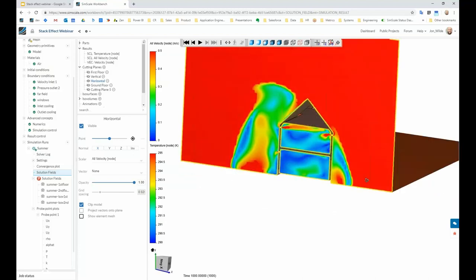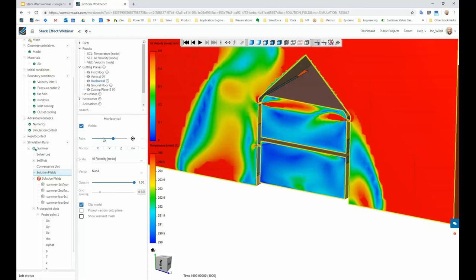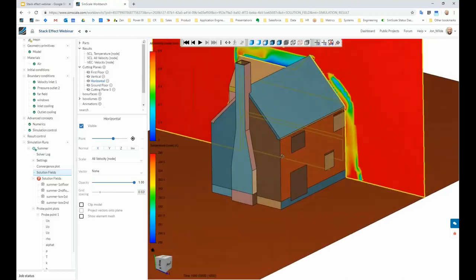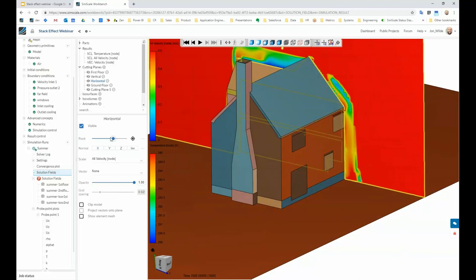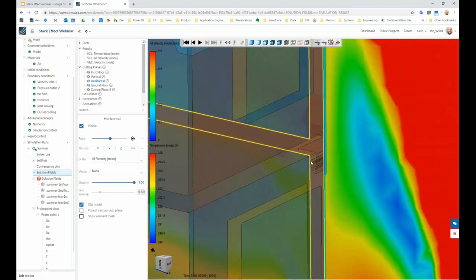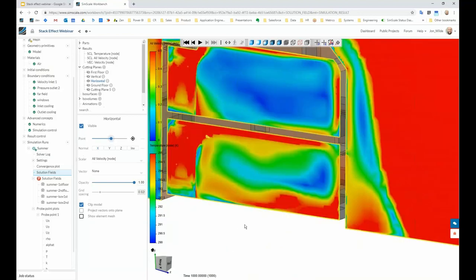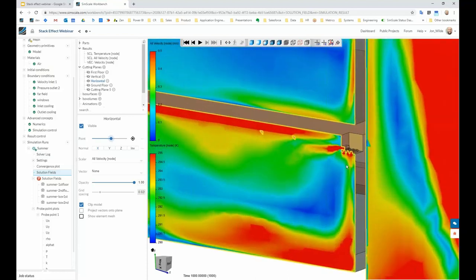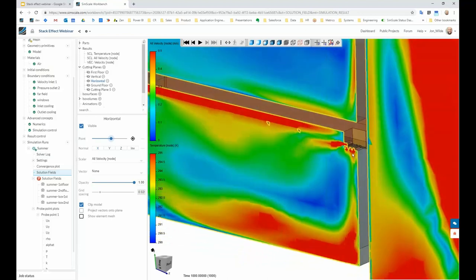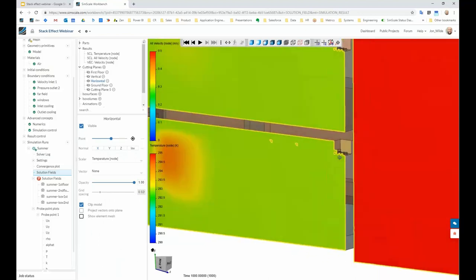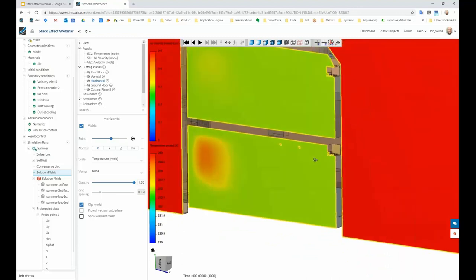Adding a horizontal plane and clipping the model to take a look at airspeed inside: with active cooling, the flow should behave a bit differently and velocities should be different. Yes, the velocities are a little bit faster, but interestingly the temperatures are uniform and comfortable. Although occupants might feel some air movement from the internal cooling, they are not likely to be uncomfortable. Spinning around to find one of the cooling units and making the model see-through: cutting through one of the units, the flow is flowing along the floor, up the wall, entering the unit and being kicked out towards the left. Looking at temperature, warm air enters underneath and cool air exits on the side — everything is so uniform it's tough to see, but that means occupants will feel very comfortable.